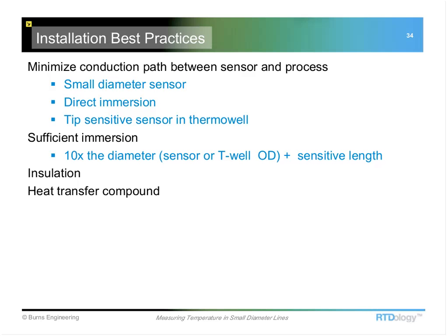For most applications, that's going to work just fine. There are some situations where you could maybe get by with a little less, and there are some where you need to actually add more than that. One that I can think of where you would need to add more would be in the situation of air temperature. I had one application where some sensors were installed in a dropped ceiling, and the probes were sticking down below the drop ceiling 5.5 inches.